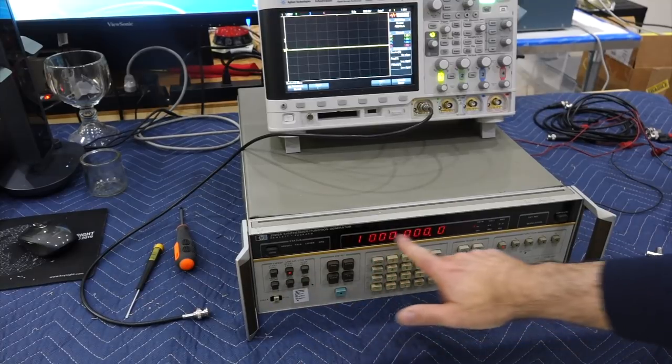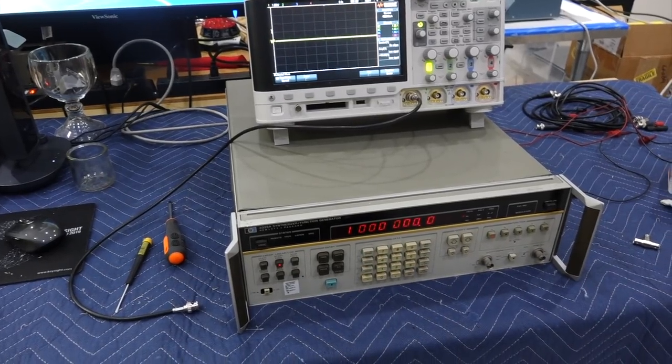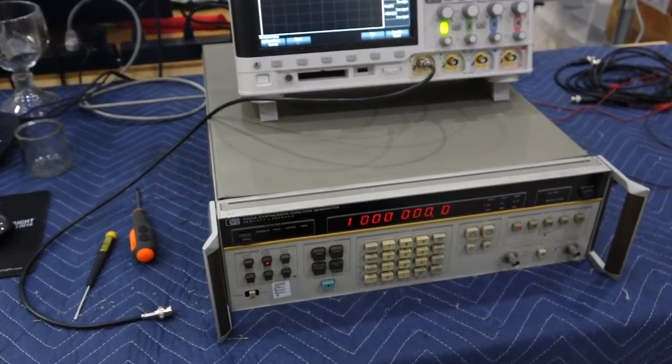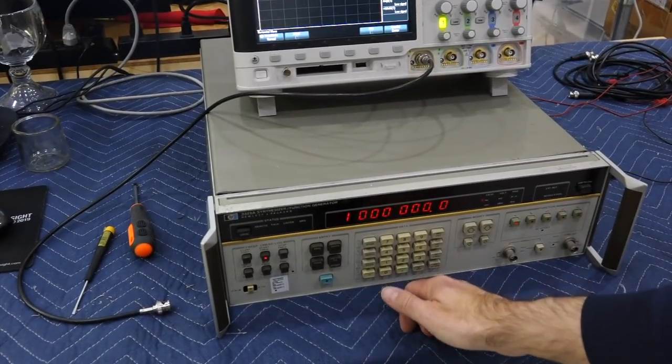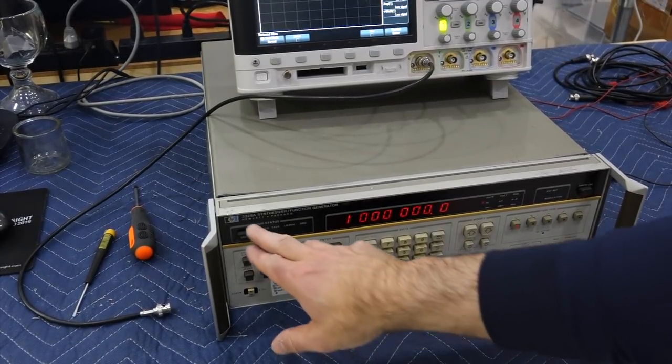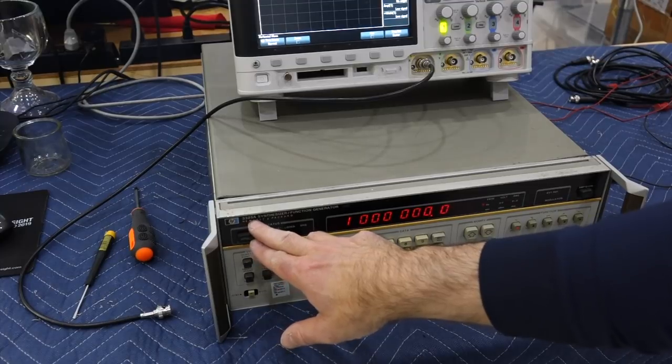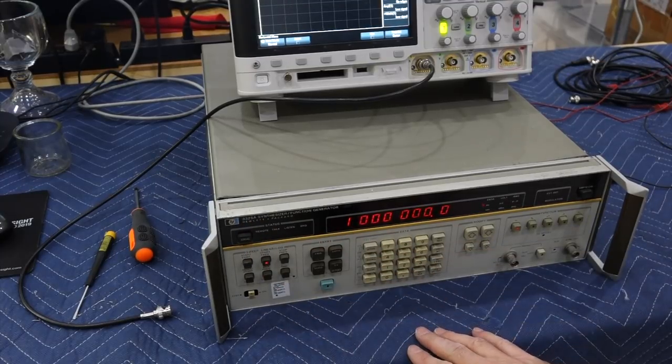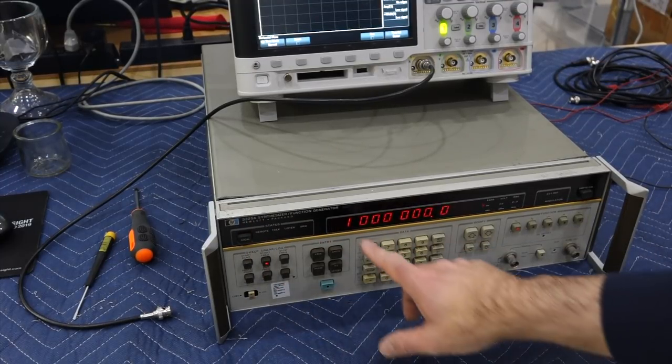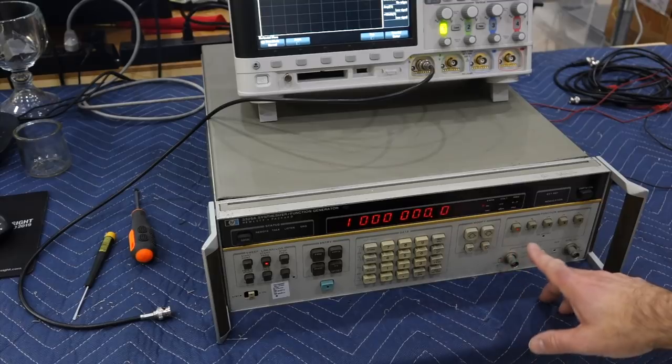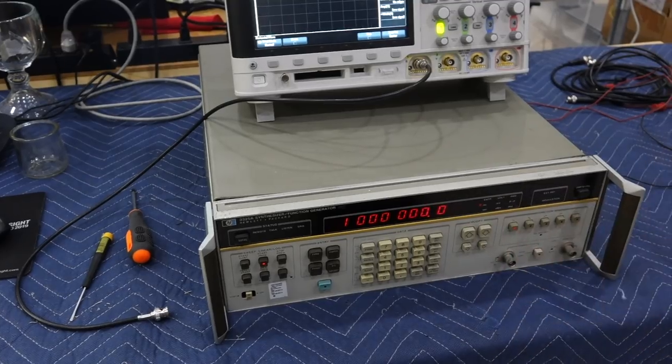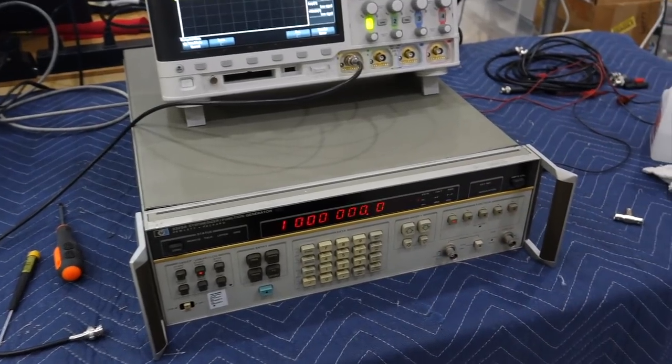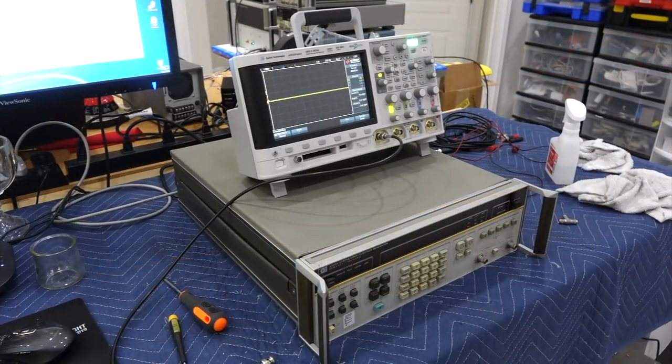So in this episode, we are going to turn to a 15 year older, but far more precise instrument, the HP3325A, which uses so-called fractional-n frequency synthesis to achieve its remarkable accuracy. But the one I have was acquired for next to nothing at an auction, and quite predictably, it does not work.